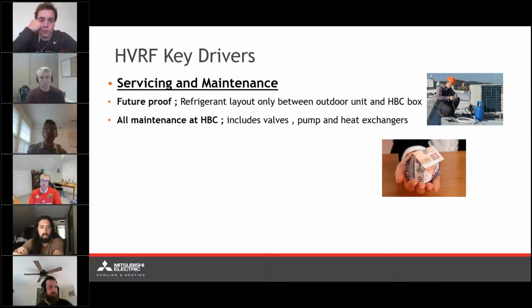And here's something interesting. All the maintenance in the system is handled at the HBC controller itself. Valves, pumps, heat exchangers, everything. We don't need to potentially go into a tenant's apartment in order to service their equipment. There's no expansion valves in the actual fan coils on these systems. Everything is located in the HBC controller itself. So if we go back to that schematic previously with the HBC in the closet, that's just where your service guy needs to go. He doesn't need to bother anyone, knock on doors, or get permission to go anywhere. Everything's just handled at the HBC.